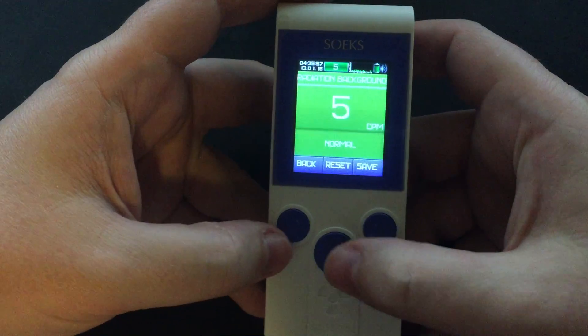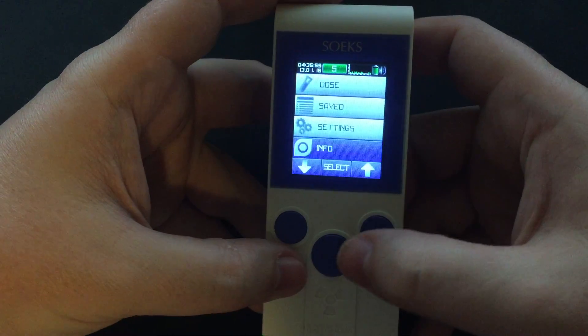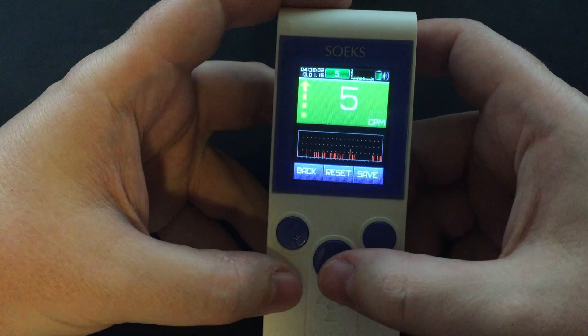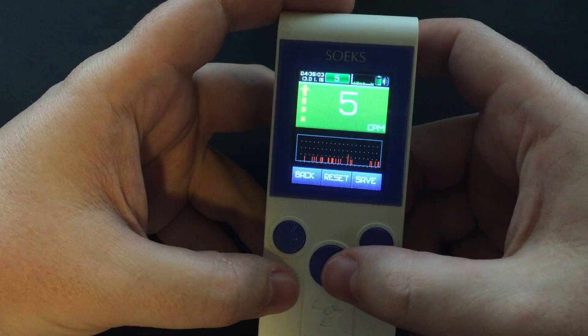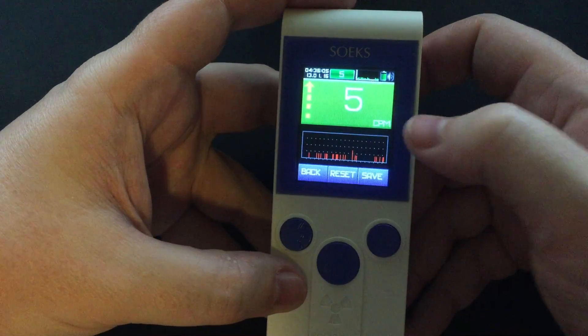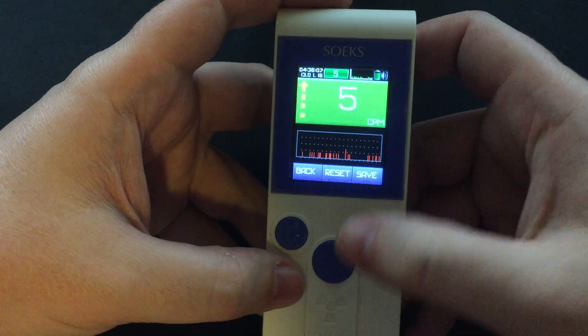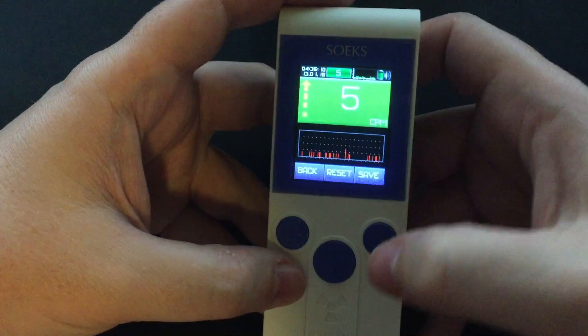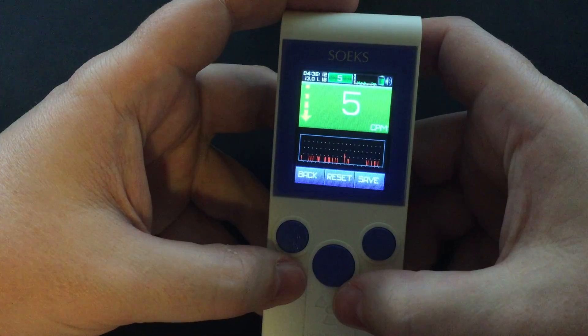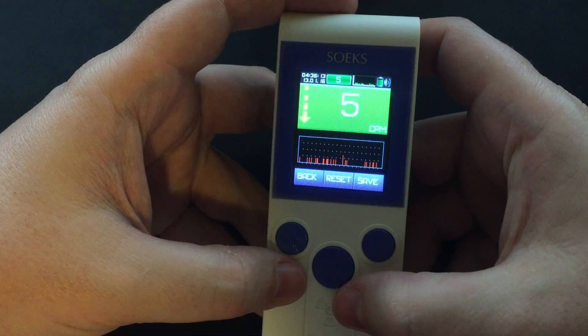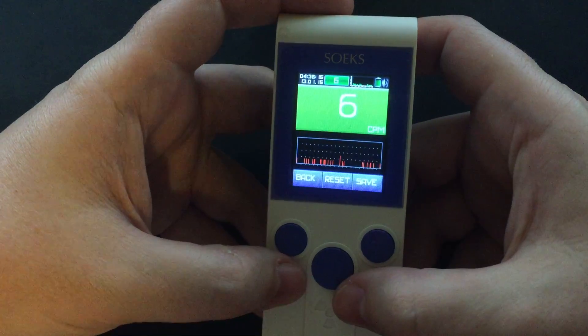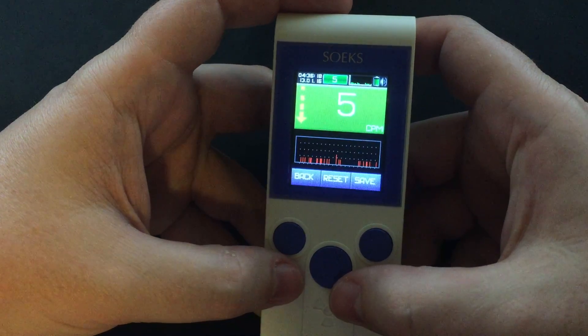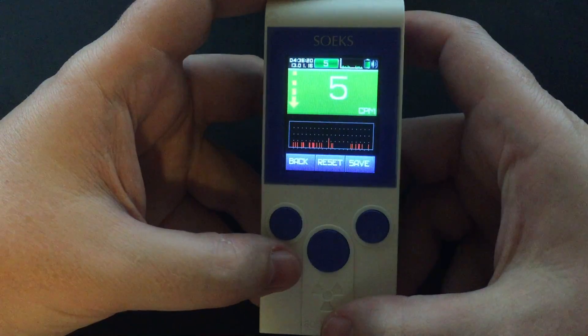This is the main menu. You can go into search mode, which does a much faster update time and has a graph so you can see the change. This will update independently of the main. If I had a strong source here — and I may demonstrate one later because I do have a 10 microcurie cesium-137 source to test these with. Right now I'm just doing a quick overview.